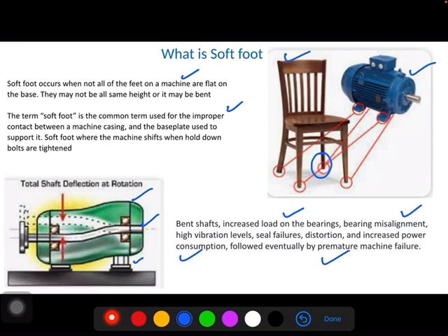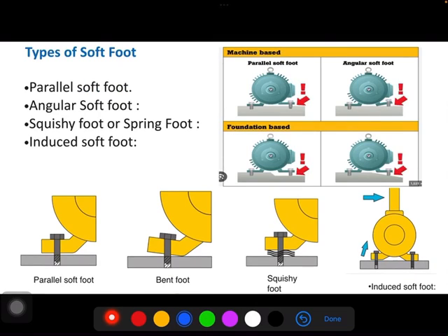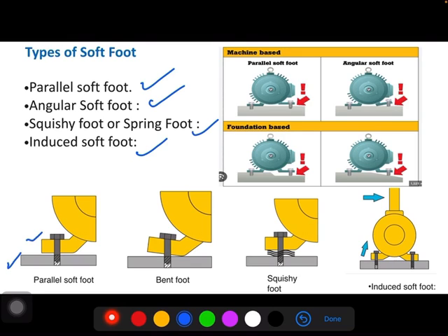So we need to understand the concept of soft foot. How many types of soft foot are there? There are mainly four types: parallel soft foot, angular soft foot, squishy foot or spring foot, and induced soft foot. What is parallel soft foot? When the machine frame feet and the base are parallel, but one of the feet on the machine is short in leg or short in length, then it is called a parallel soft foot. This happens either when the motor feet leg is short or there will be a different elevation of the concrete.